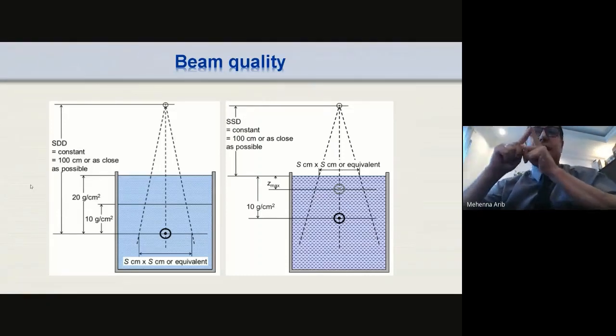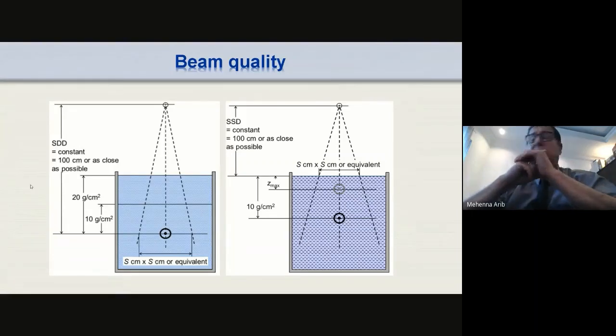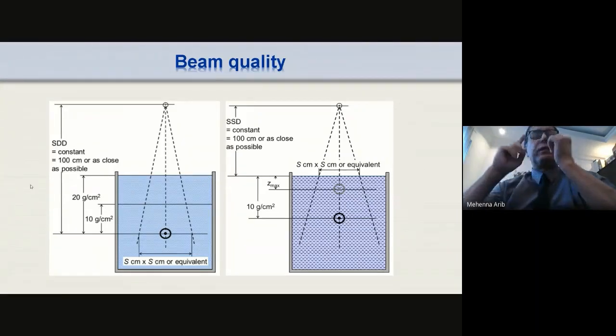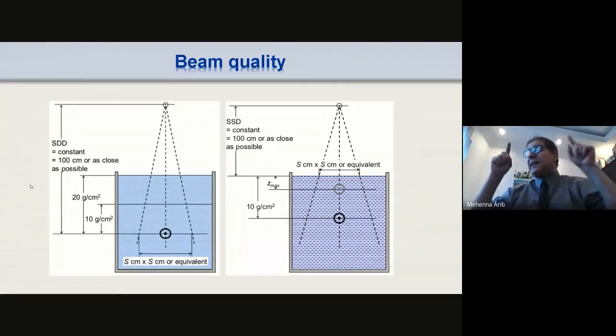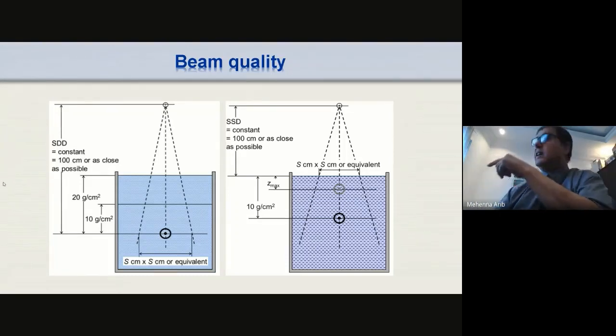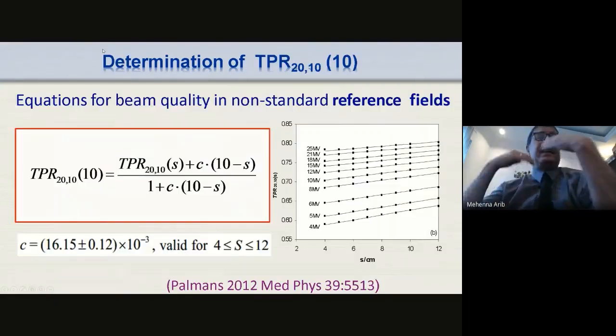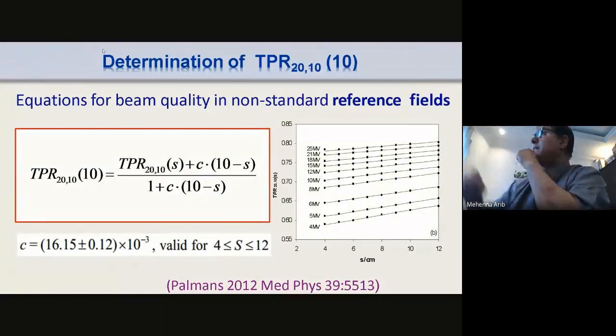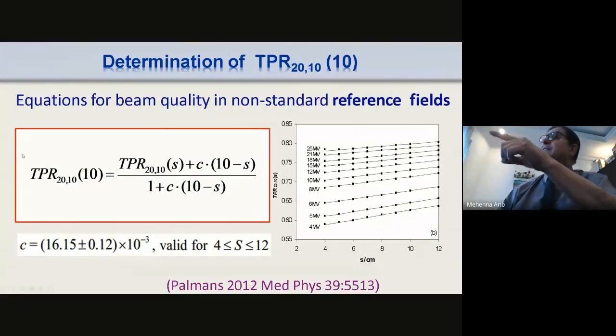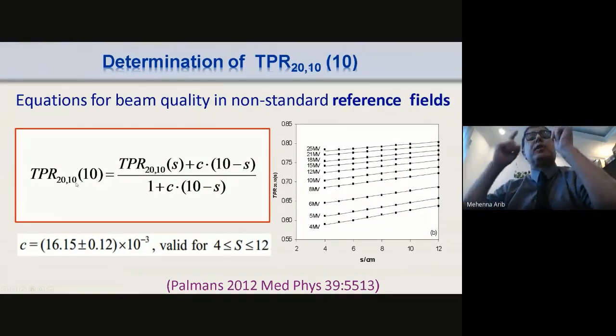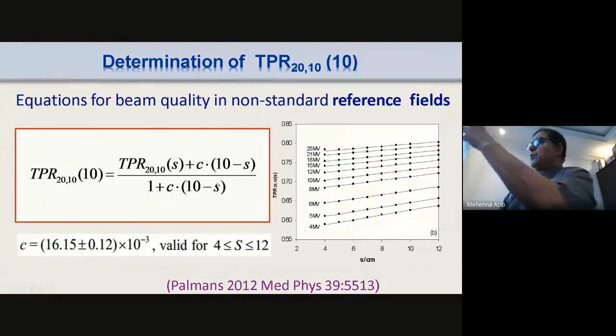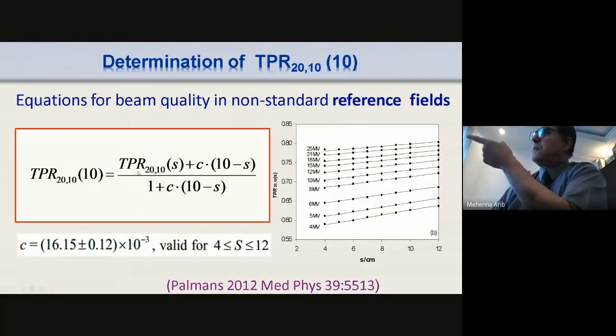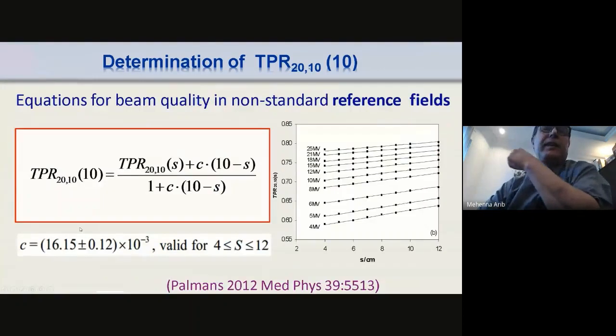For the TPR, remember the conversion factor for the absorbed dose calibration coefficient: you need to calculate the TPR 20,10, which is not available for the small MSR field sizes. So you need to find a way to calculate the theoretical TPR 20,10 from the TPR for the small fields. So we use this well-known configuration to measure the quality index for the small field. And then Palmans, in the code of practice, gave this equation which converts the TPR 20,10 for the MSR field or for the small field, and calculates the theoretical TPR 20,10 for 10 by 10, which is used actually for calculating the conversion factor. So this factor is given either from the TPR 20,10 or also there is another equation from the percentage depth dose at 10 by 10.